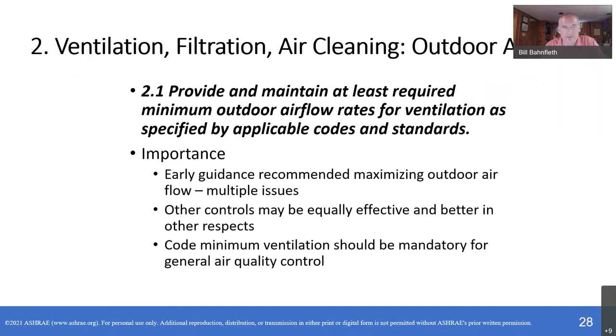I think maybe the most important section of the guidance, or at least the one that addresses some of the key issues, is ventilation, filtration, and air cleaning. And the first item here is that we recommend providing at least the minimum outdoor airflow rates required by code. Why is it important to say this? First of all, because the early guidance was extreme. It said bring in as much outdoor air as you can. And in fact, many, not ASHRAE, were recommending to not have any recirculation and just go 100% outdoor air.